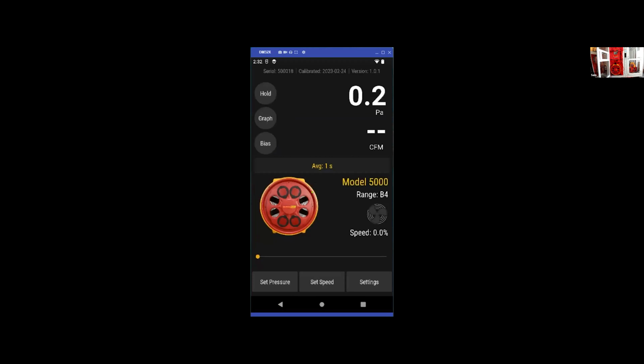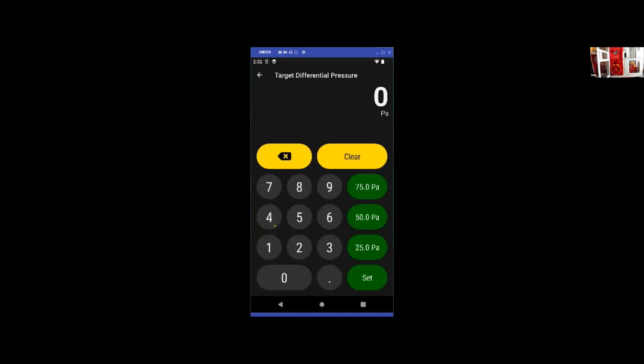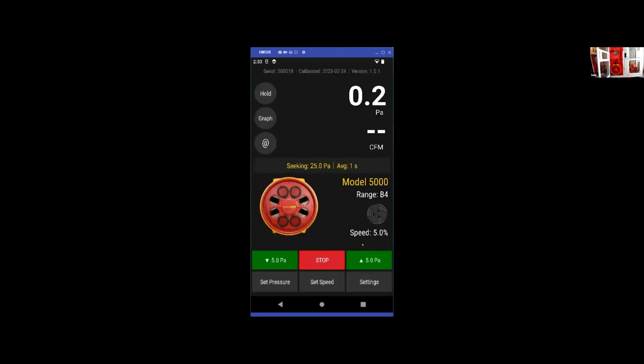Something else you'll see on this screen is options to set pressure. So if I wanted to run a blower door test, I can enter it on the keypad just like on the DM32, but we also put a few hotkeys in here. These are the three most common target pressures we see in air tightness testing: 25 for residential duct testing, 50 for residential blower door, 75 for commercial blower door. You can just quickly tap those to seek that pressure.